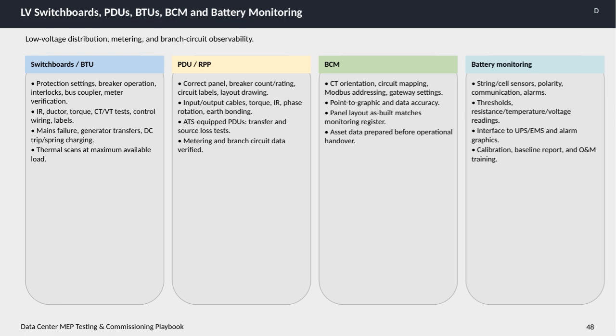Finally, for battery monitoring, we assess string and cell sensors for proper polarity, communication integrity, and alarm functionality. Threshold settings along with resistance, temperature, and voltage readings are closely monitored. Integration with UPS and energy management systems is verified, and alarm graphics are checked for clarity. This phase also includes calibration, baseline reporting, and operator maintenance training to ensure ongoing reliability and safety.